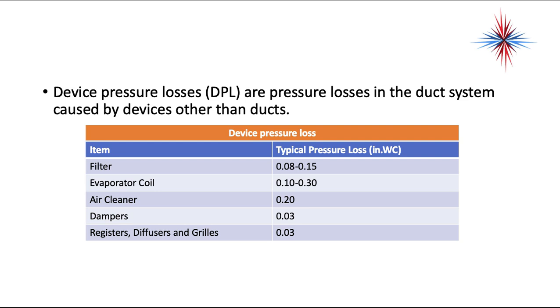From a service technician standpoint, this is extremely important to understand. You have to take static pressures every time you have a service call, because people add things over time. A system may have been set up properly originally, but if someone added an air cleaner or a very tight filter, the static pressure may no longer work properly with the system.